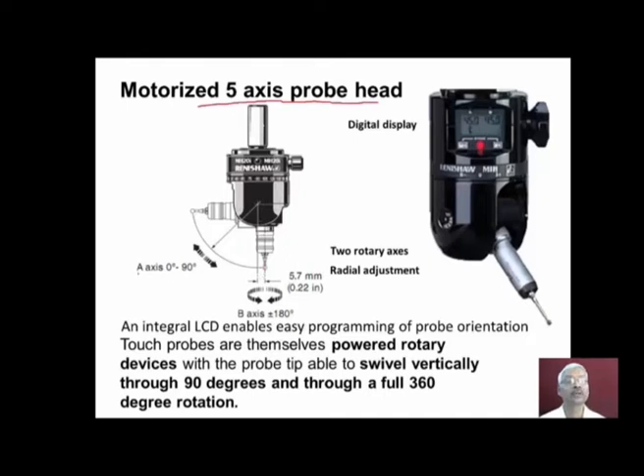We can observe here that apart from XYZ motion given by the CMM structure, these motorized probe heads have their own A-axis movement as well as B-axis movement. So the stylus can be swiveled as shown here, and the stylus can rotate plus 180 degrees or minus 180 degrees. Apart from that, a radial adjustment is also possible.